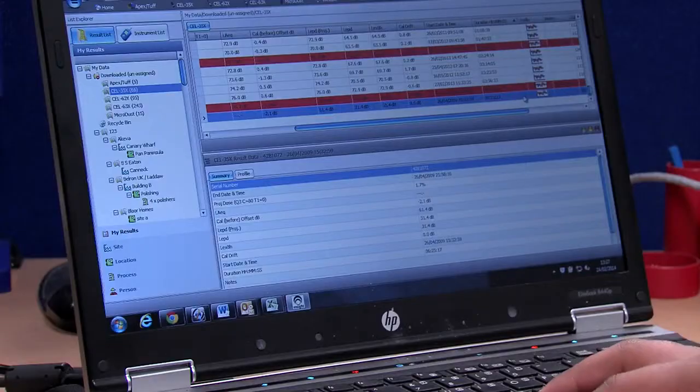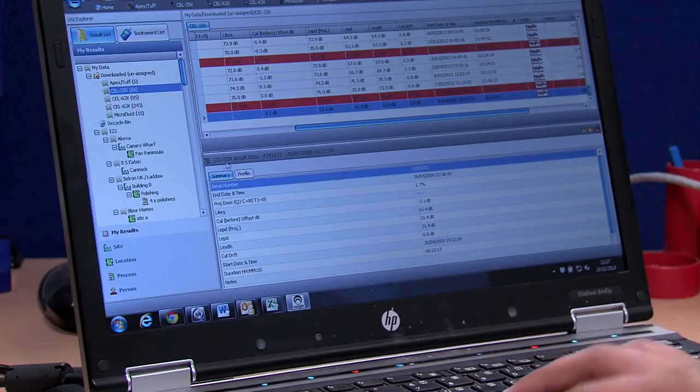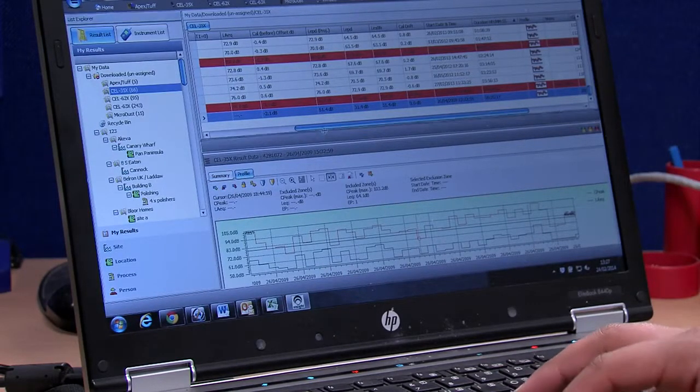Place the Casella 120 series calibrator over the microphone and the dBadge will do the rest with its auto-calibration feature. The dBadge connects to a PC using InSight data management software via the infrared download cable provided. Once downloaded to InSight, data can be analysed and reports generated so that appropriate action can be taken.